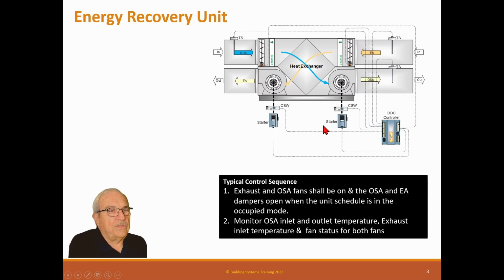So the sequence is the exhaust and outside air fan should be on, and the outside air and the exhaust air dampers open when the unit is scheduled in the occupied mode. Monitor the outside air inlet and outlet temperatures, exhaust inlet temperature, and fan status for both fans.